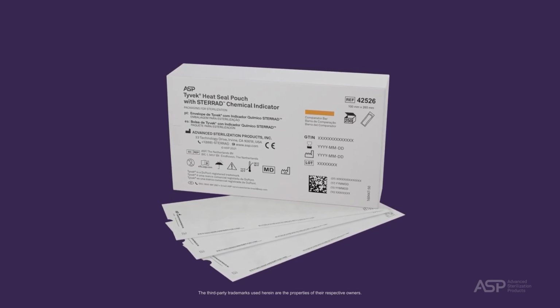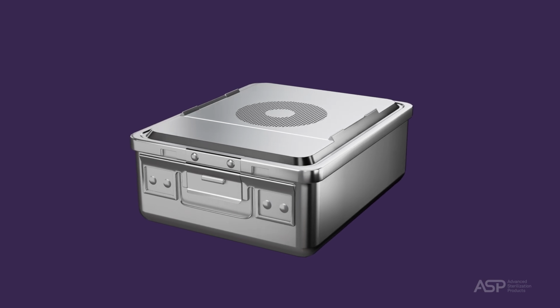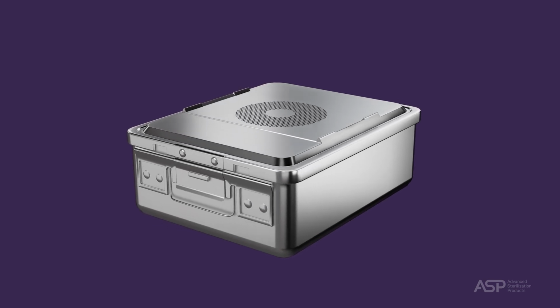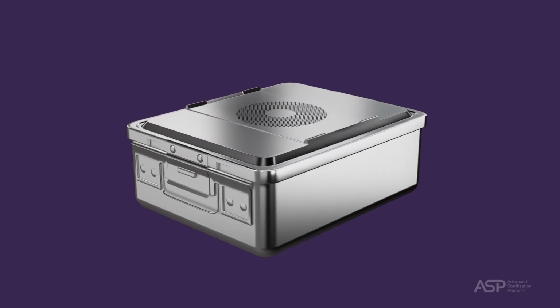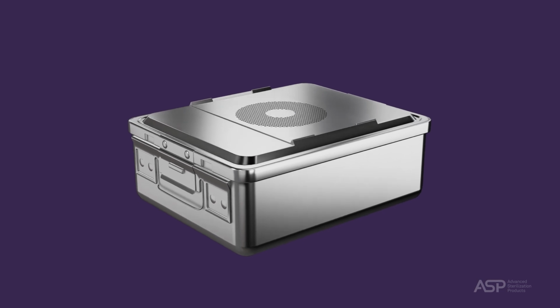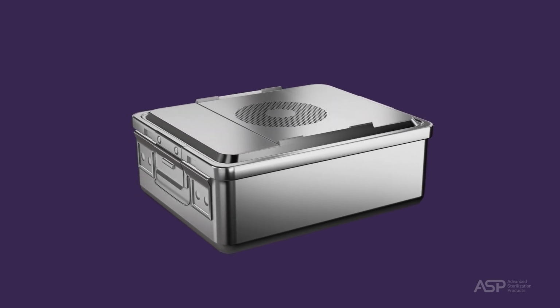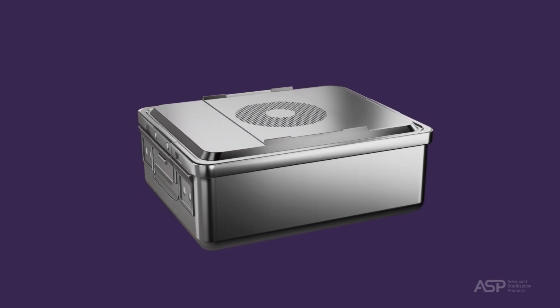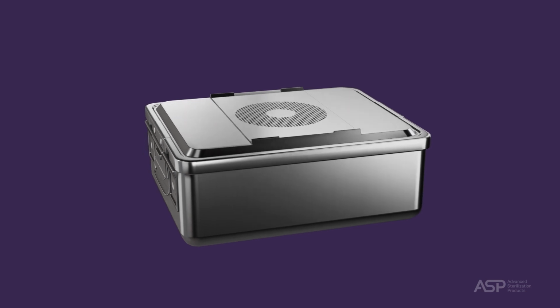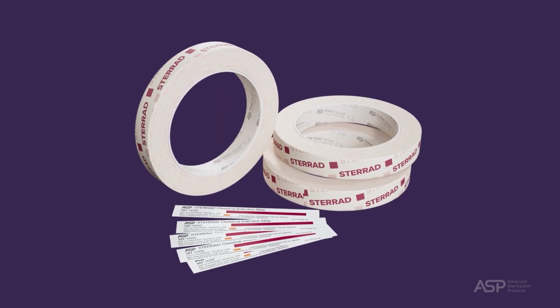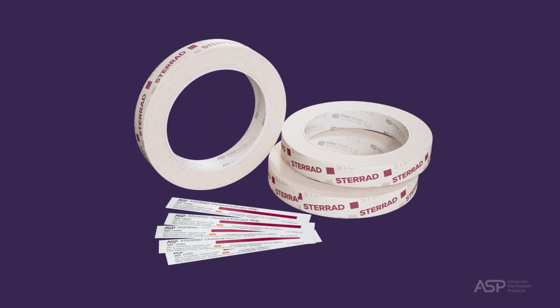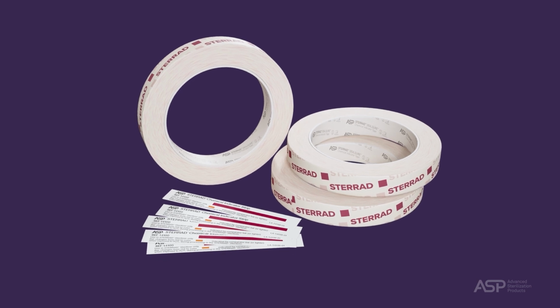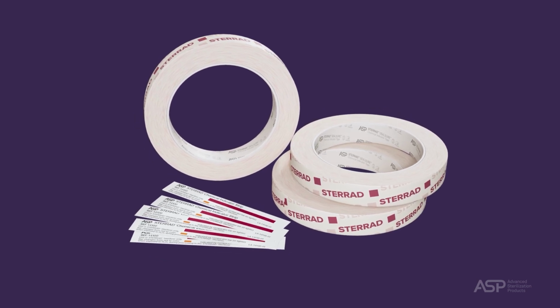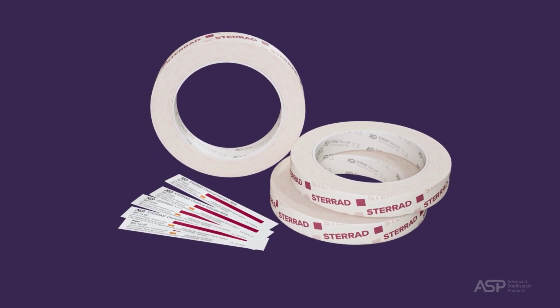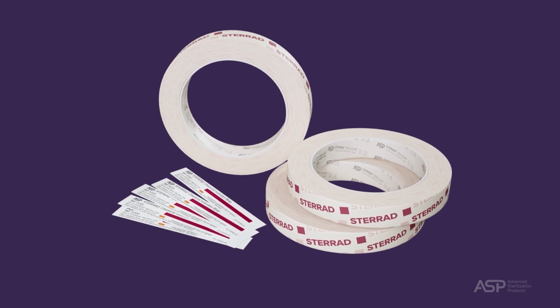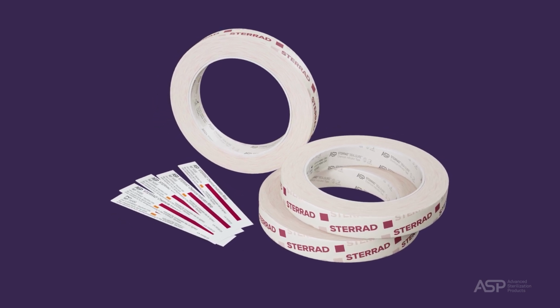validated by ASP. If you are using rigid containers cleared by the FDA for use in the STERRAD 100NX Sterilizer, follow the instructions for use provided by the manufacturer. Verify that the rigid containers are cleared for use in each sterilization cycle. STERRAD chemical indicator strips and SealSure chemical indicator tape offer a method to verify that the load has been exposed to hydrogen peroxide in the sterilizer. Chemical indicators are not a substitute for biological indicators.